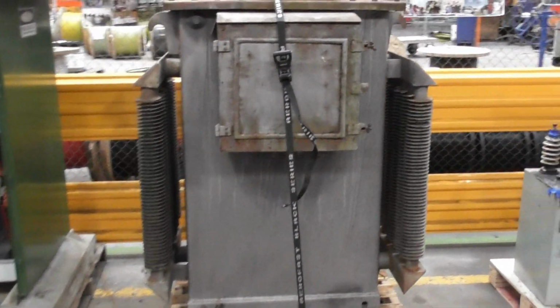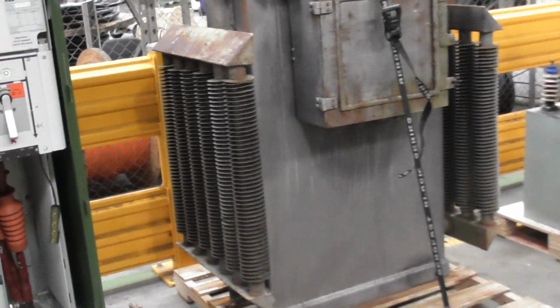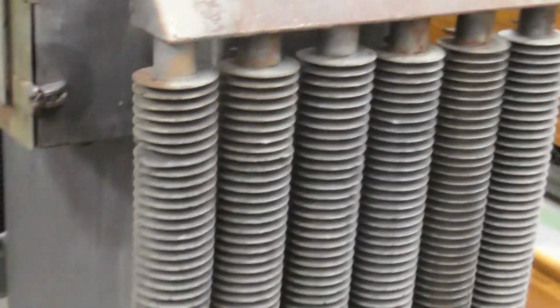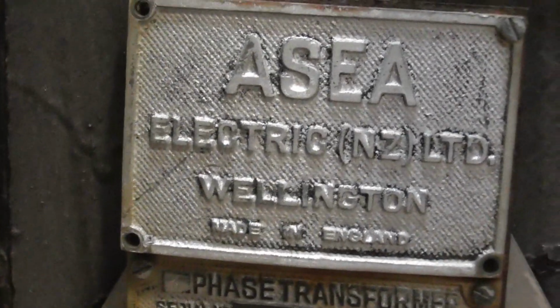Good old ASEA. That will go to the scrapper, unfortunately. It's a pity, because it's a really cool transformer. The way they make these fins. What happened, I saw the pre-removal photo. This wire is broken off in the wind over the years, so these wires are pretty flexible. So you can see if they're sitting in there for 30, 40, 50 years, they could break off, which happens, unfortunately. So yeah, that's the problem with this beautiful device.